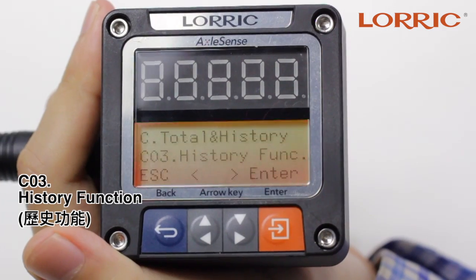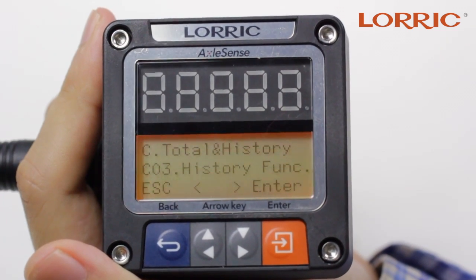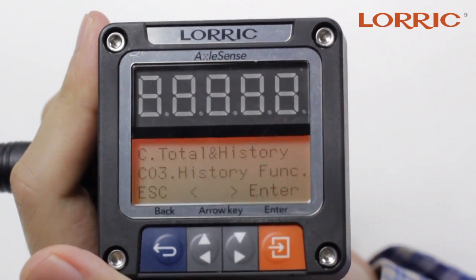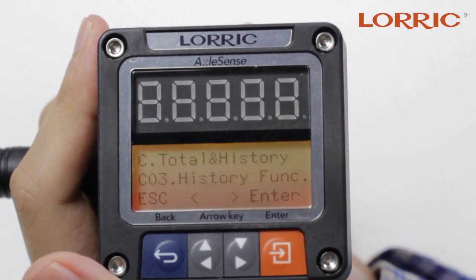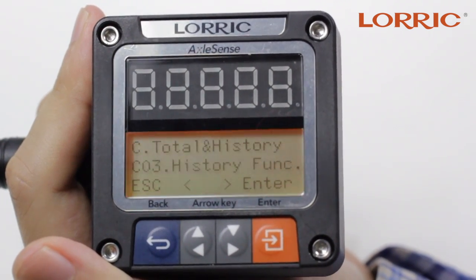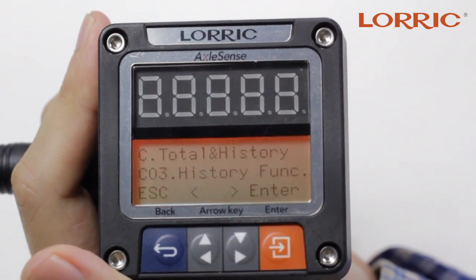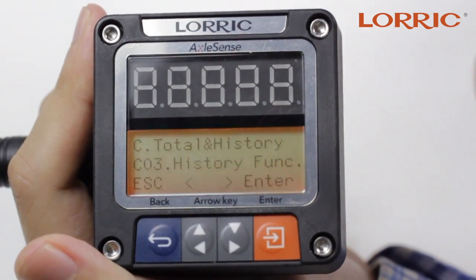The next option is C03, which is the history function. This is a very interesting feature of the paddle wheel flow meter — it keeps track of up to 14 days of flow rate information. In other words, it works as a data logger. Before turning on this function, there are two things you need to know. First, you would have to insert a CR2032 battery inside of the paddle. We will create another video showing how to remove and install this battery. It's very simple and easy to do.